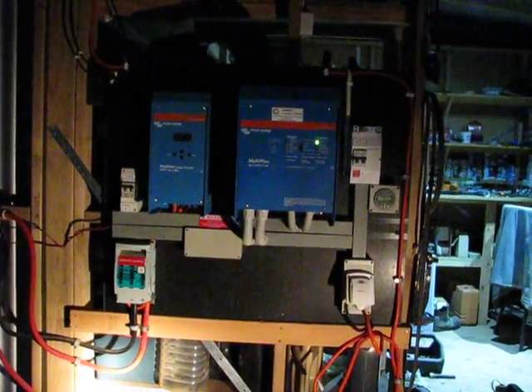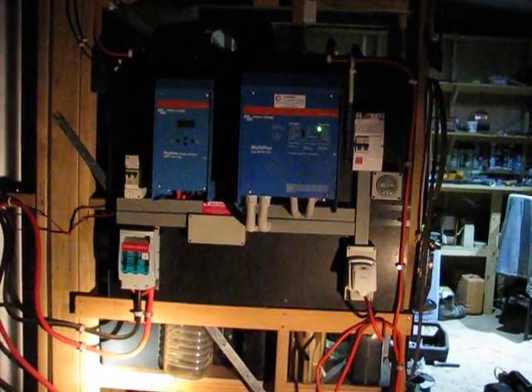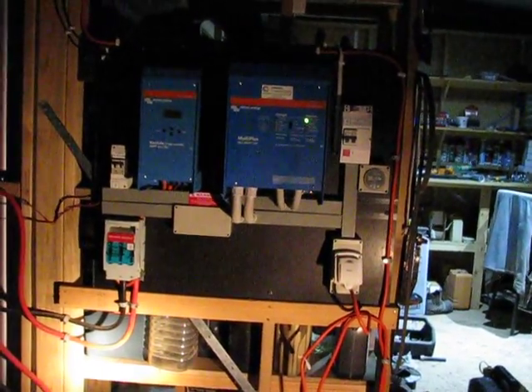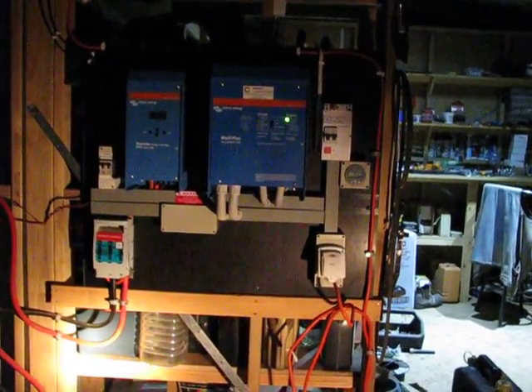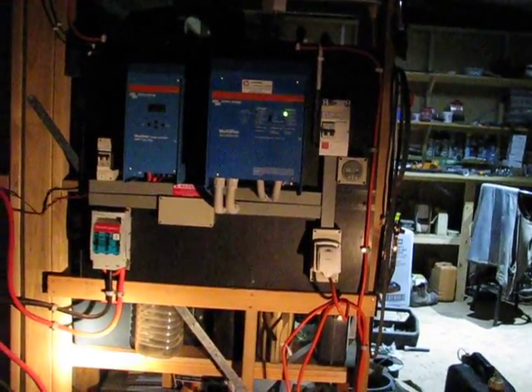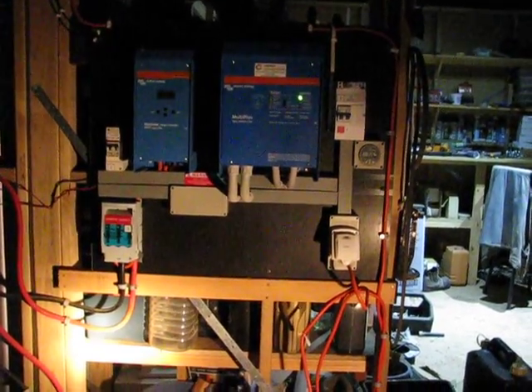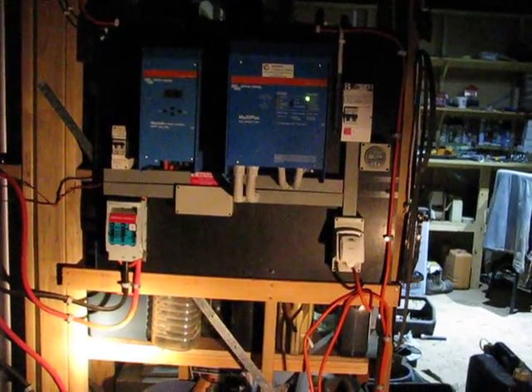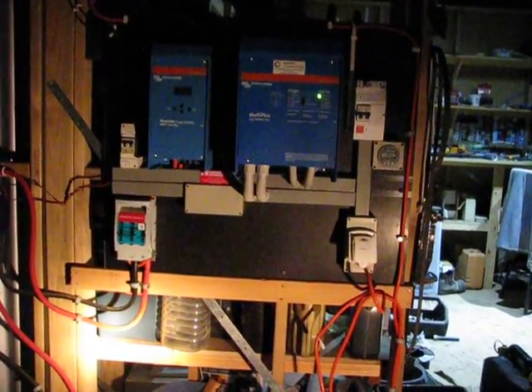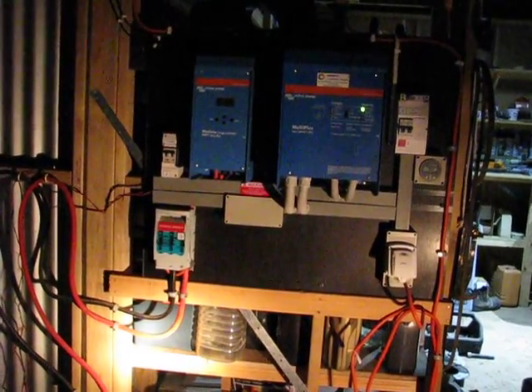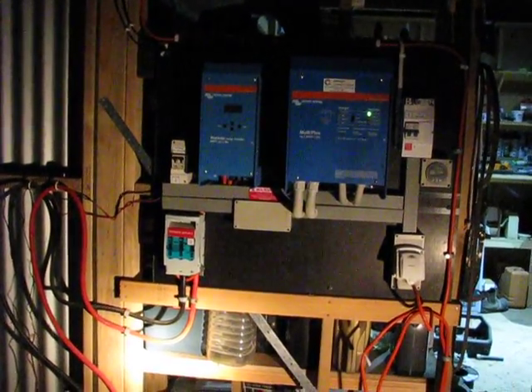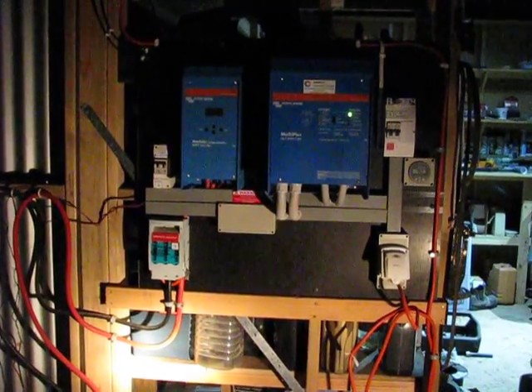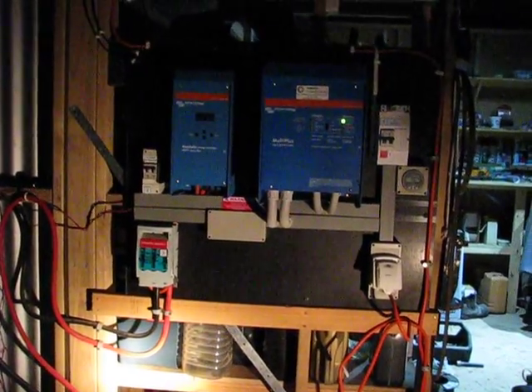That reduces the lifespan of the batteries. So there's a simple video about batteries. You can buy the batteries and equipment, and the salesman will tell you 15 years life cycle. But if you hammer those batteries and drop them down to 50-60% every single day because you're a power guzzler, you might want to think about putting a small generator on and maybe a battery monitor to stop those batteries going down so low. That will extend the life of those batteries hugely. I can't emphasize this enough. I don't care whether you've got lead acid or forklift batteries, if you discharge them very deeply, it uses a really large amount of the battery life up.